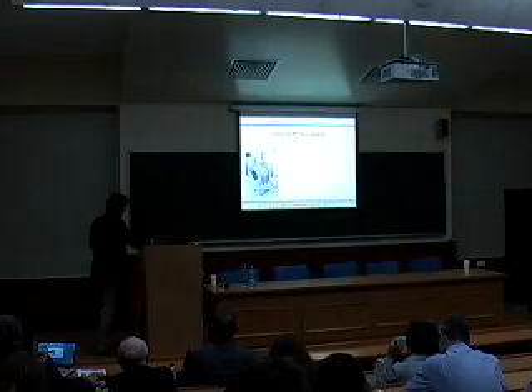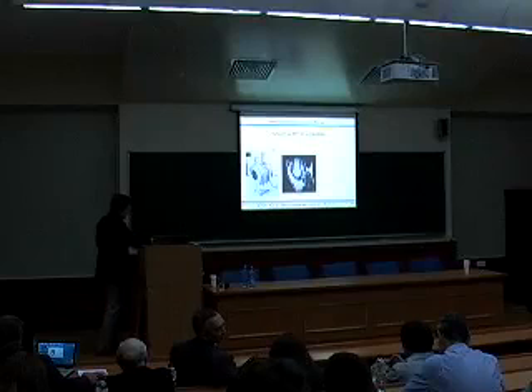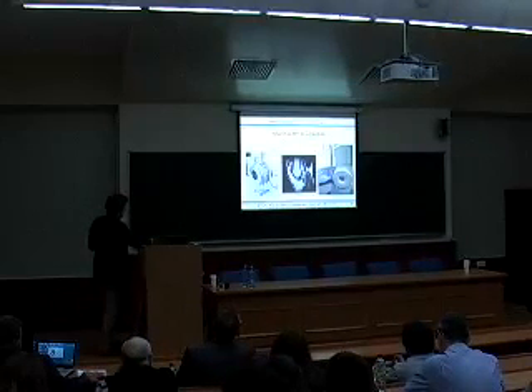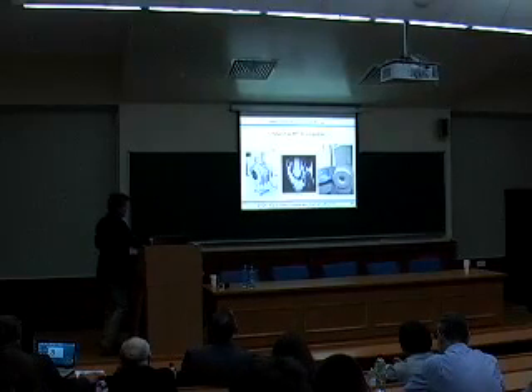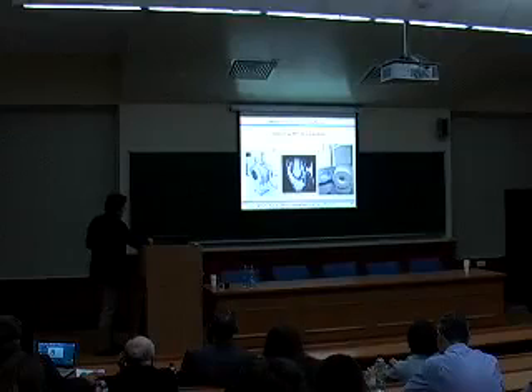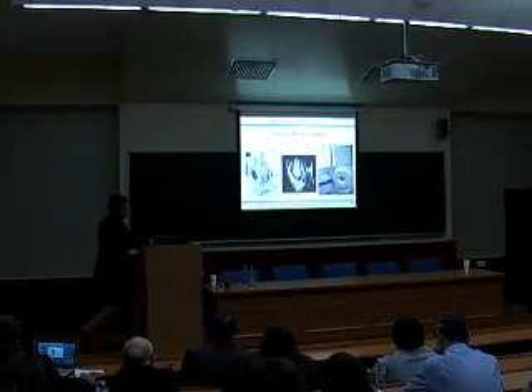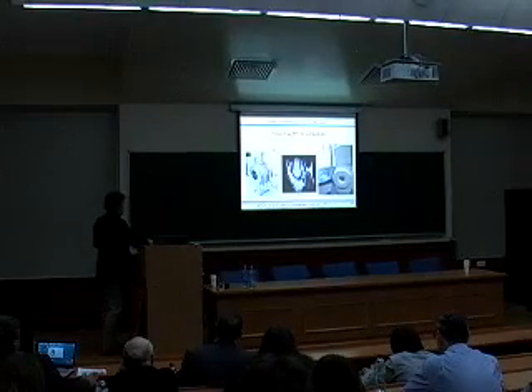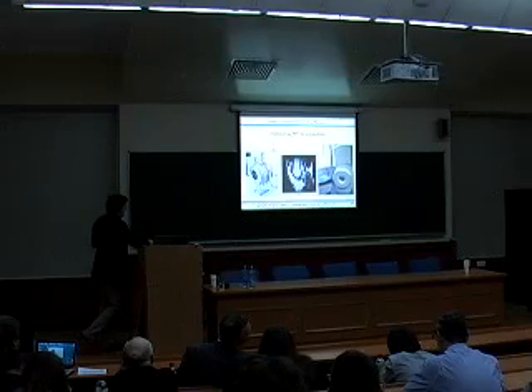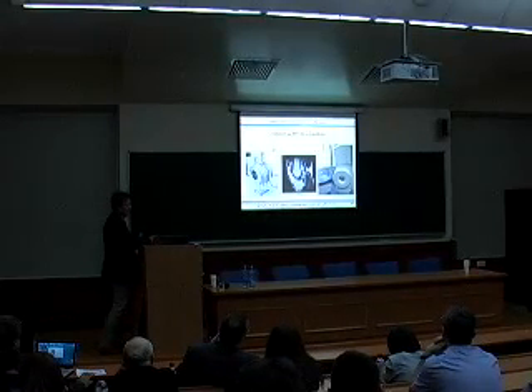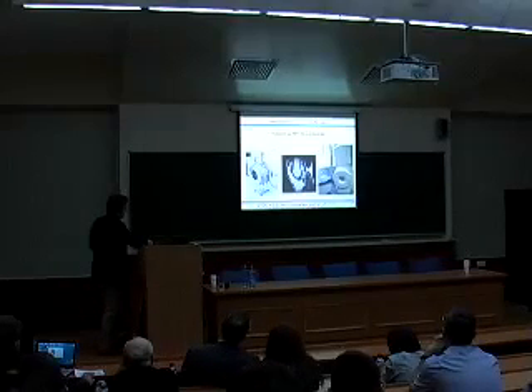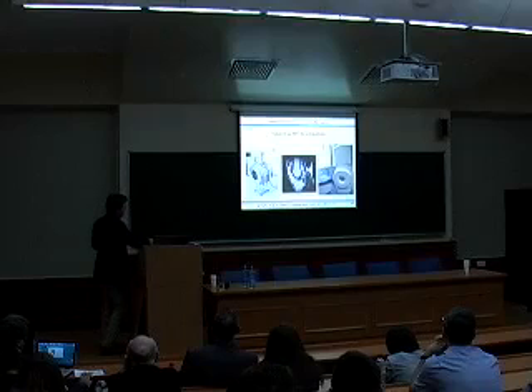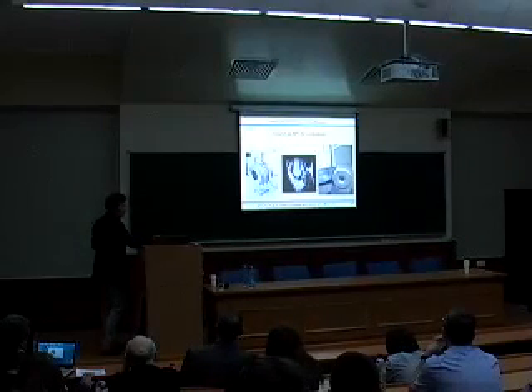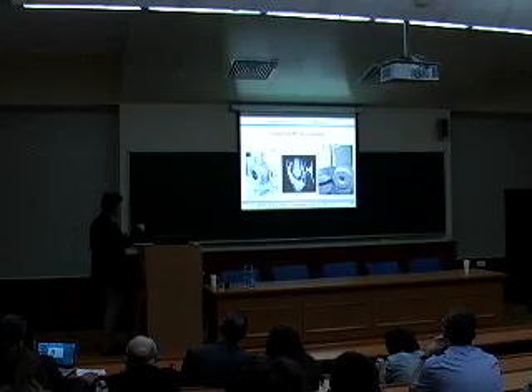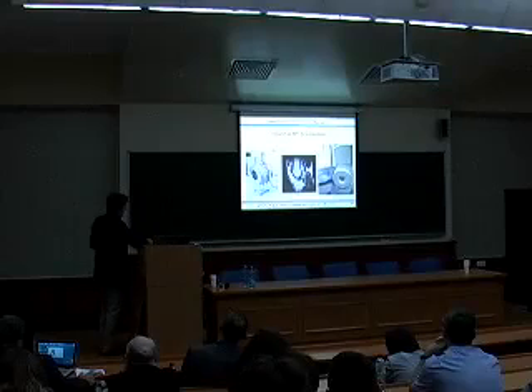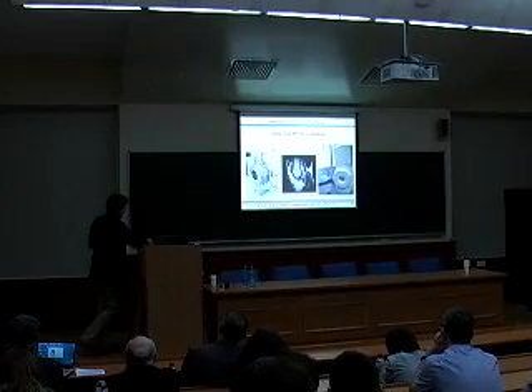Important is this picture because we started and realized in this case helium-free technology. It means that inside of the helium vessel we have no helium. It's vacuum. And it is the so-called conductive method of cooling. We cool not the superconductor directly, but the support for the superconductive wire. It's working very safely.